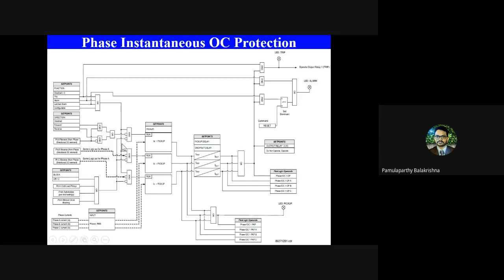Apart from voltage, the major difference in the logic diagram is that you also require a direction. The direction of the current, whether it's a directional relay or non-directional relay, is defined. And if it is a directional relay, whether it's a forward direction or reverse direction also has to be given as input to the logic. The direction of the current will be analyzed by the relay and given as input to the logic for executing.